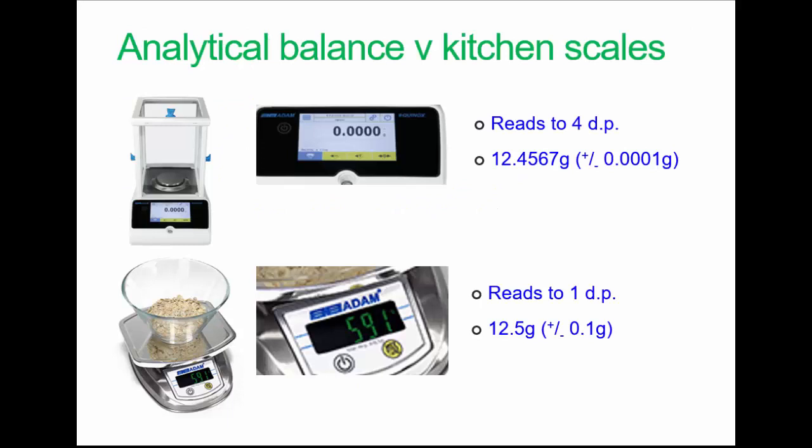In the food lab, we have analytical balances which read to four decimal places and food kitchen scales which read to one decimal place. We can get a weight on the analytical balance to six significant figures, whereas on the kitchen scales we're going to get three significant figures. You couldn't report the weight you record from the kitchen scales as 12.5000, for example. It could only be 12.5, plus or minus 0.1, compared to a much narrower margin for the analytical balance.